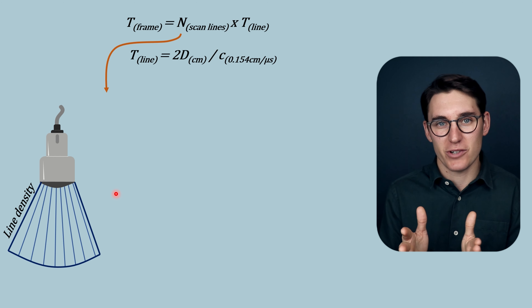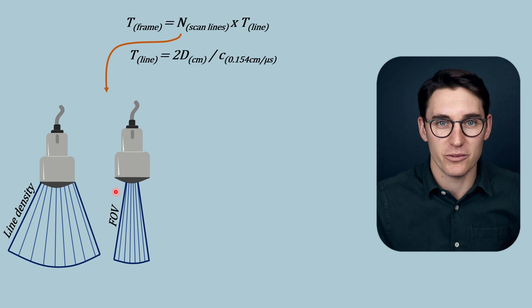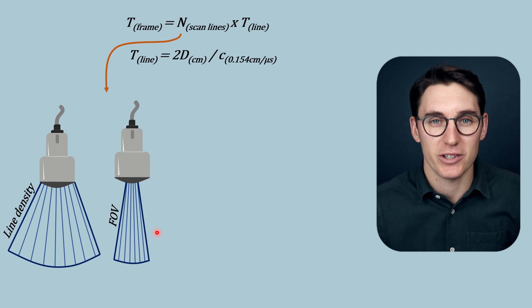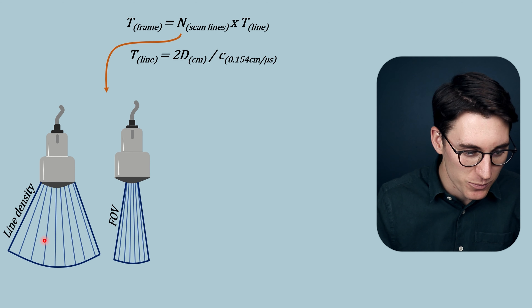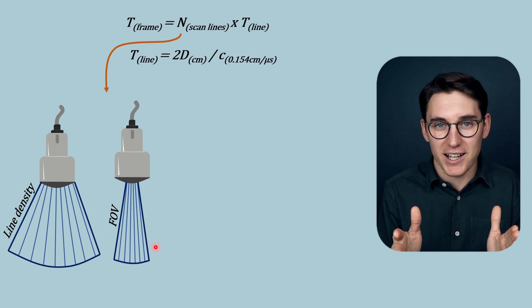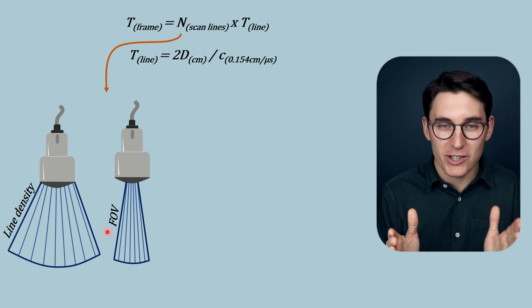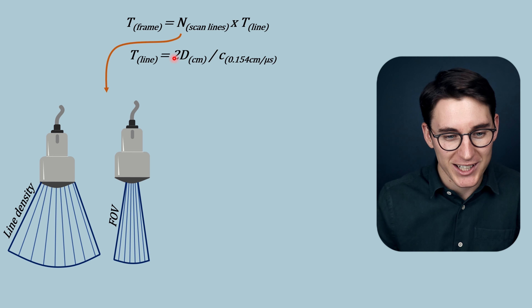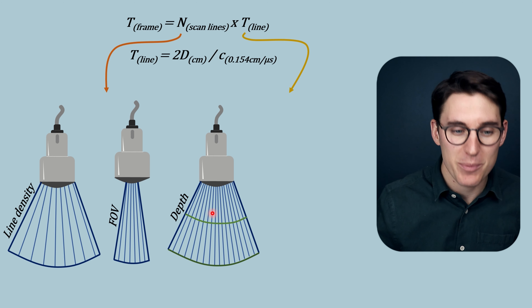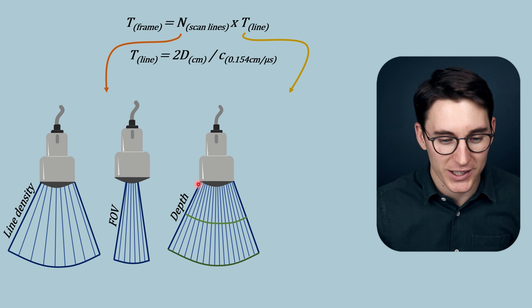If we don't want to sacrifice lateral resolution, we can reduce the number of scan lines by narrowing the field of view. Our line density remains the same, but we've reduced the total number of scan lines by narrowing the field of view. For example, if scanning a kidney with a cyst in one small region, we could narrow down the field of view — effectively reducing scan lines, giving a quicker frame rate and better temporal resolution. Additionally, reducing depth reduces the time to acquire a single A-line; halving the depth doubles the frame rate.